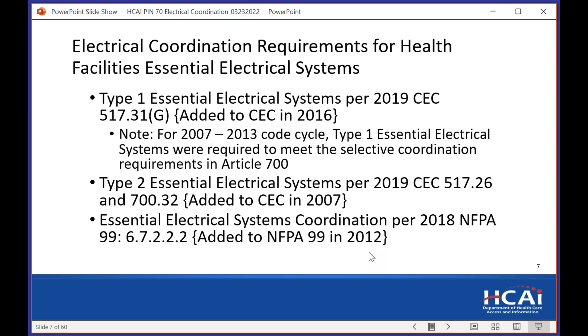And this aligns with what you will find in NFPA 99, that essential electrical system coordination is required for type 1 and type 2 essential electrical systems. For those who are familiar with CMS, the coordination requirement was added to NFPA 99 in 2012. So projects that are required to meet the CMS requirements would be required to meet coordination.